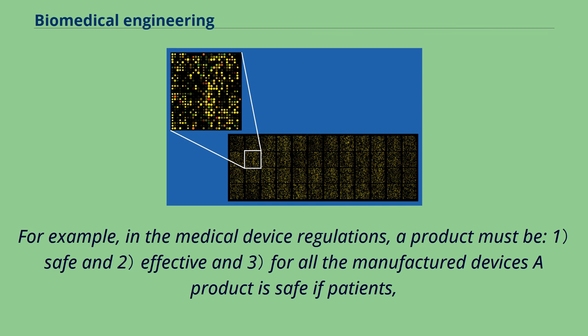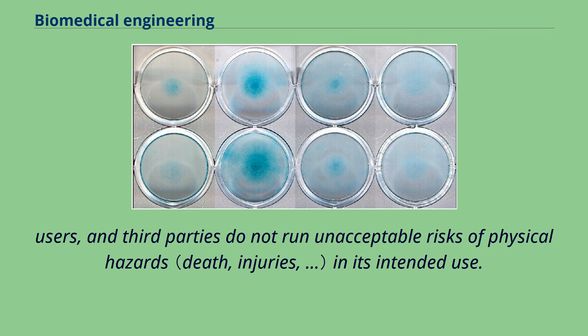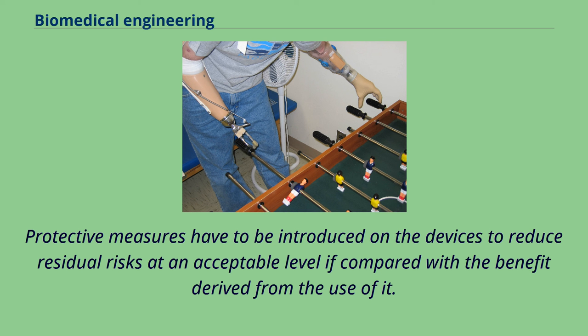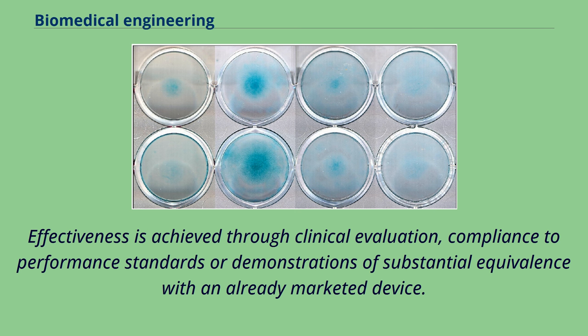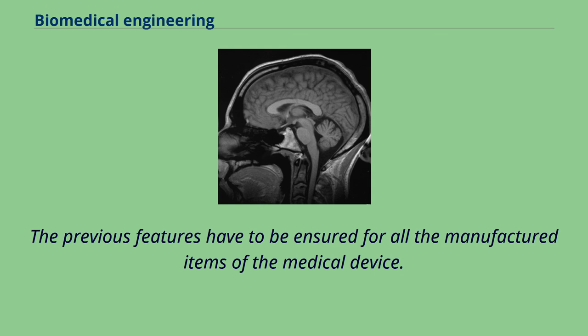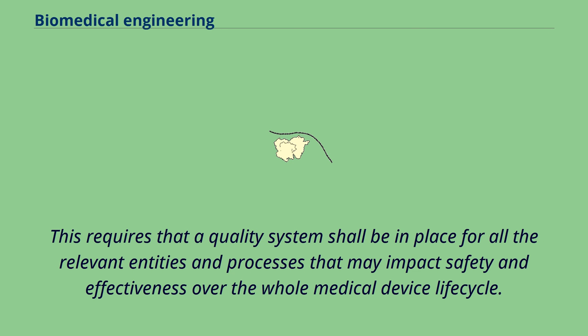In medical device regulations, a product must be: (1) safe, (2) effective, and (3) consistently manufactured. A product is safe if patients, users, and third parties do not run unacceptable risks of physical hazards in its intended use. Protective measures have to be introduced to reduce residual risks to an acceptable level. A product is effective if it performs as specified by the manufacturer in the intended use. Effectiveness is achieved through clinical evaluation, compliance to performance standards, or demonstrations of substantial equivalence with an already marketed device. A quality system shall be in place for all relevant entities and processes that may impact safety and effectiveness over the whole medical device life cycle.